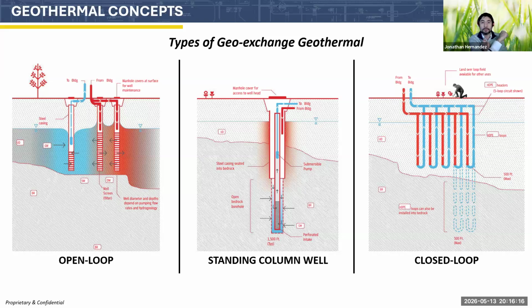Fast forward to the closed loop solution that we will talk about in detail today. Closed loop means circuits of boreholes with a high density polyethylene pipe, flexible, going down into each borehole, designed in circuits to interact via a manifold with a heat pump—water to water, water to air. It can be hybridized with an air source, meaning a heat recovery chiller, 6-pipe system. There are several ways to make it work. But the point is, you're no longer depending on aquifers, no longer permitting for wells, and no longer requiring pumps exposed to the elements in the subsurface.